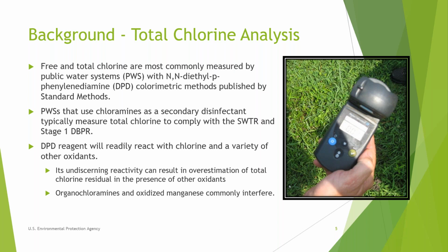in terms of quantifying disinfectant residual in water systems. So chloraminated systems, or systems that use chloramines as a secondary disinfectant, typically measure total chlorine to comply with the Surface Water Treatment Rule and the Stage 1 DBP rule.